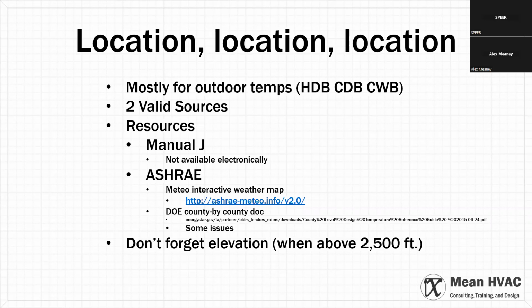Then there's one other factor. If they had their temperatures right, but weirdly their location was way off, a pretty weird scenario, but I've seen people just try to change, like national builders. Sometimes they'll try to update a design where they'll just change the outdoor temperatures to match properly. But if they're using a design for Indiana in Texas, which I saw once, it actually throws off the cooling load. The latitude that you're at actually has an effect on solar gain in the Manual J. That is a step in the process if you're doing it by hand. You actually have to look up a table that has solar heat per latitude or per latitude range. And the more southern you get, the higher that number becomes. So there is yet another little factor.